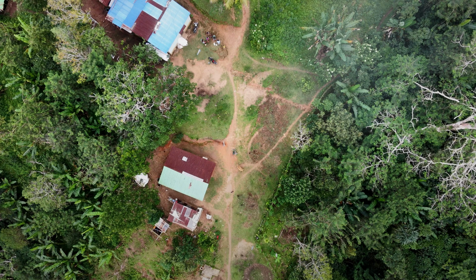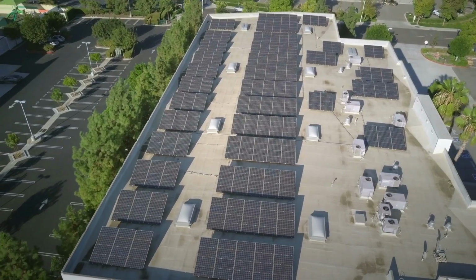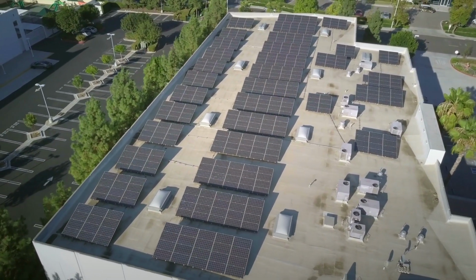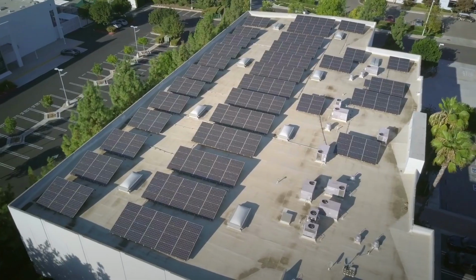The math is watts multiplied by run hours. 10 watts for 2 hours is 20 watt hours. 60 watts for 5 hours is 300 watt hours. Add every row. Then add a loss buffer. For a beginner system, use 20 to 30% because controllers, inverters, wiring, temperature, and battery behavior all take a bite.